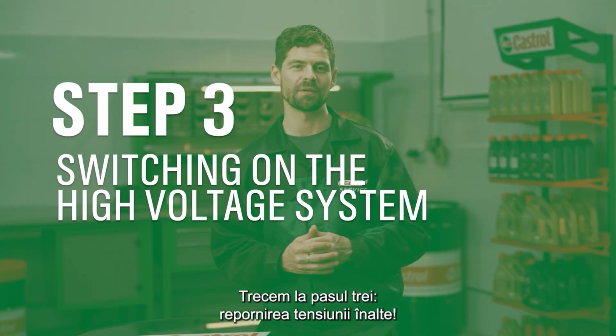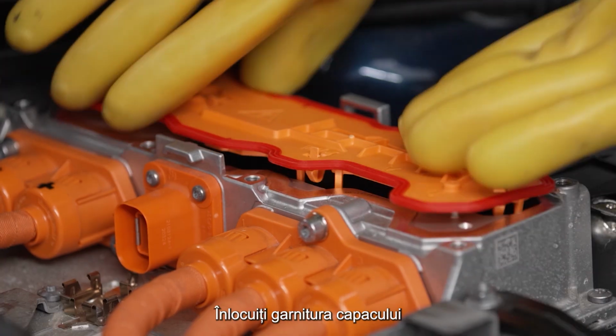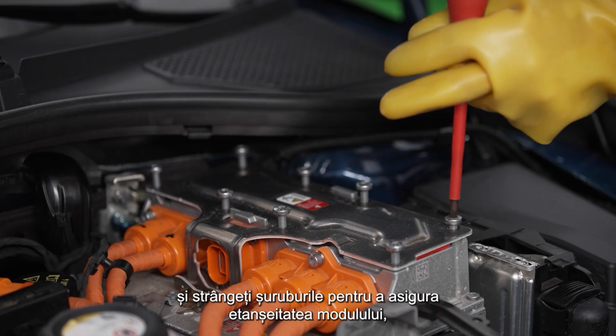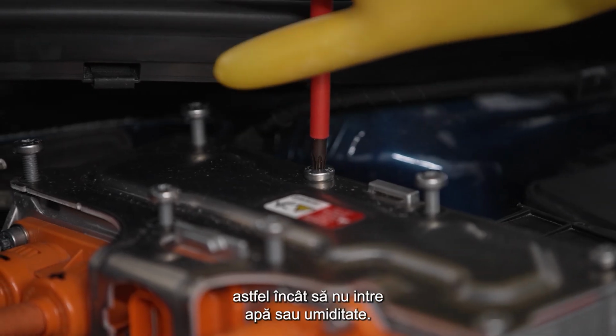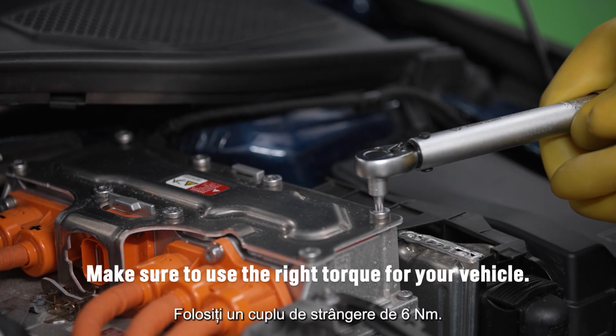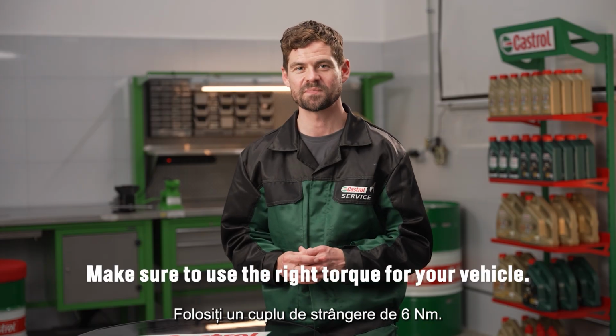On to step number 3. Switching the high voltage back on. Replace the cover gasket and tighten the screws to ensure the tightness of the power module so no water or moisture can get inside. Use a torque of 6 Newton meters for this.